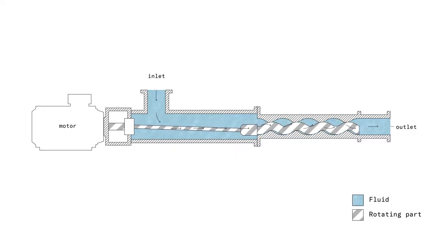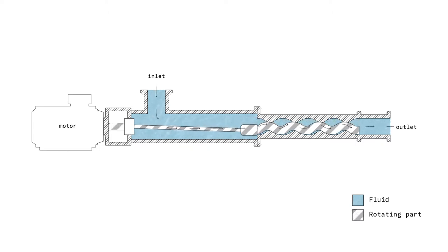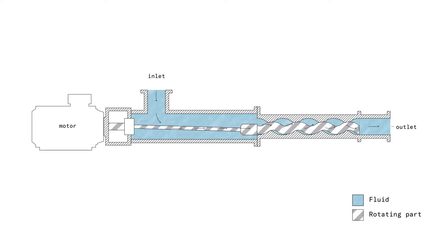We have a very nice animation where I'm going to explain how it works inside the pump. In front of us we see the animation of the PC pump. All the way on the left we have the motor. In the center we have the driving shaft for the rotor, and on the right hand side we see the rotor and the stator. The stator is just standing still and the rotor is making the motion, going up and down — it's actually spinning inside the stator.